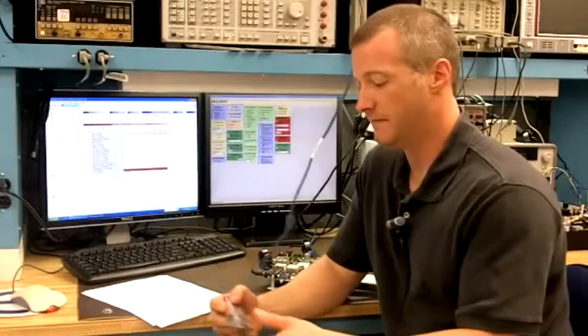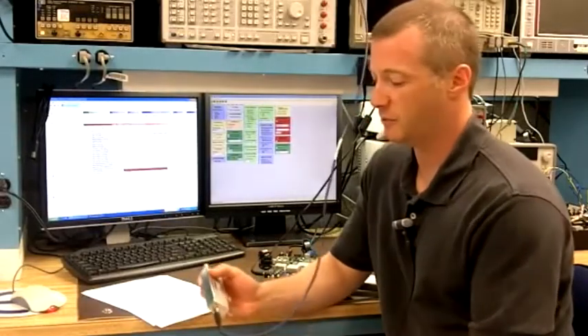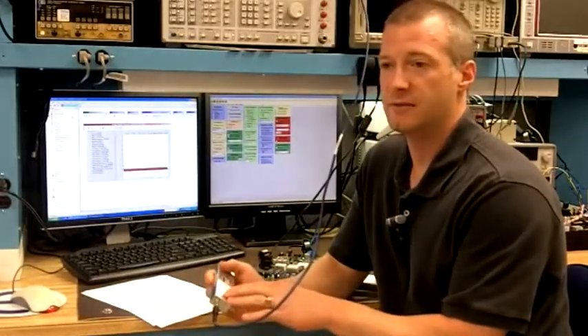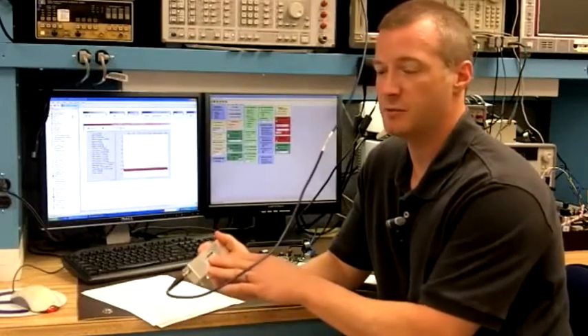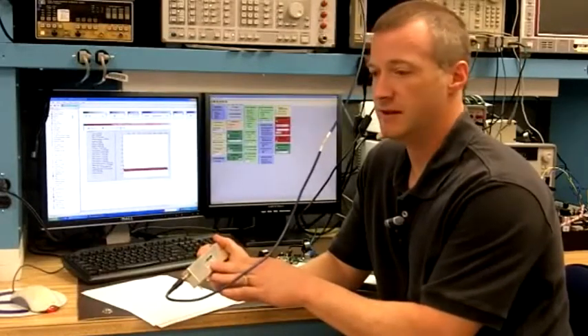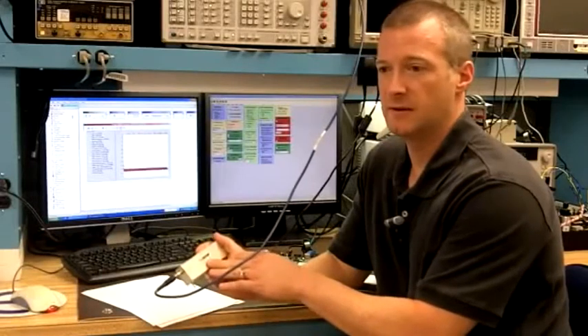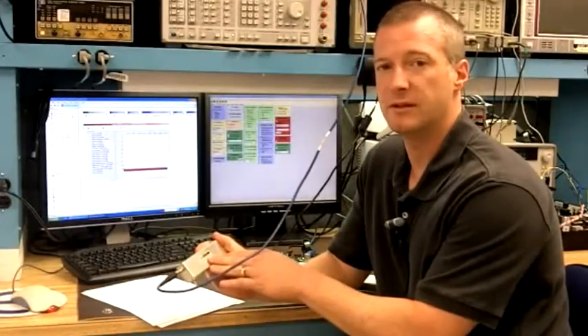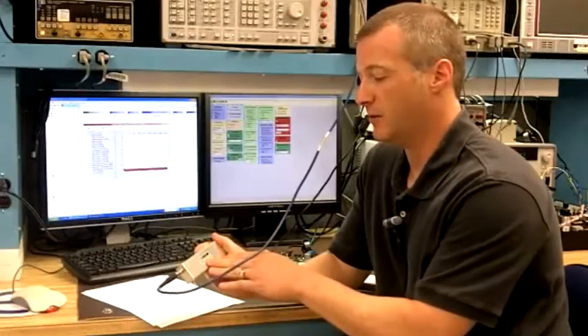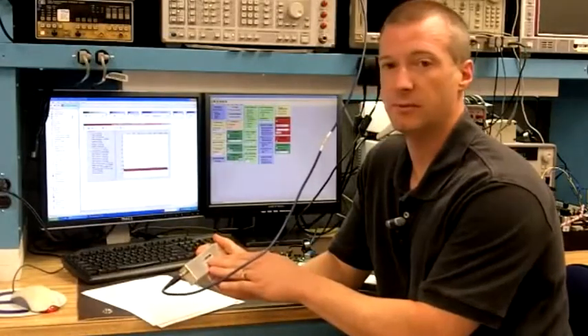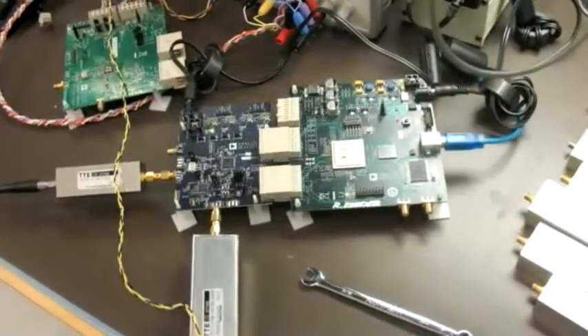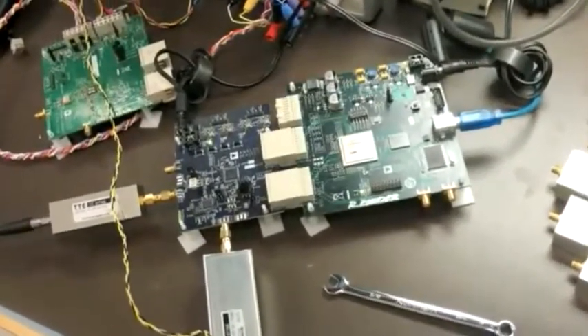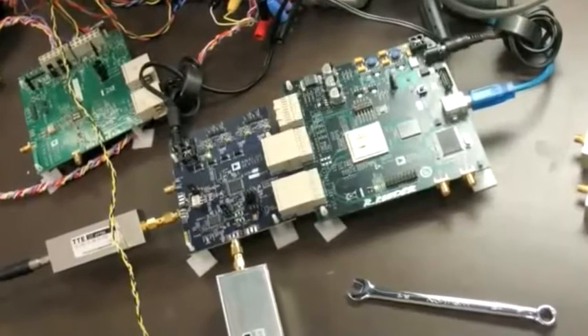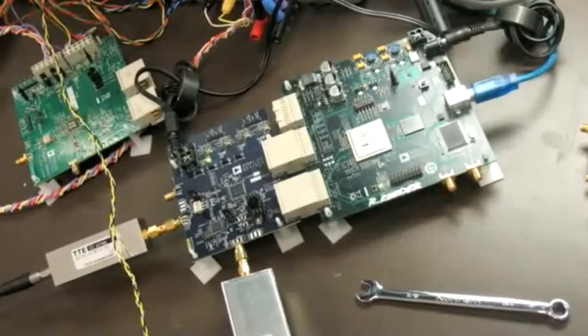In order to ensure that I get the best performance, I should note that all signal generators have some amount of spurs, so I'm going to filter out the spurs of the signal generator using TTE filters such as this. We use bandpass filters of 10% or less bandwidth, and seventh-order ellipticals. So I simply connect this up to the analog input, and then I turn it on.